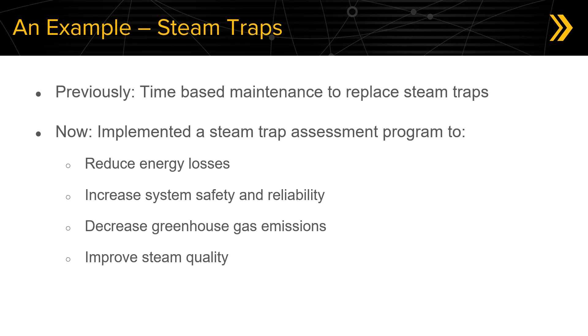Well, for each steam trap, we actually went out with two devices: an infrared detector that could detect heat, and a mobile device. Specifically, what we were looking for was whether each steam trap was installed and working correctly, and if not, whether the trap had been misapplied or failed in the open or closed position.